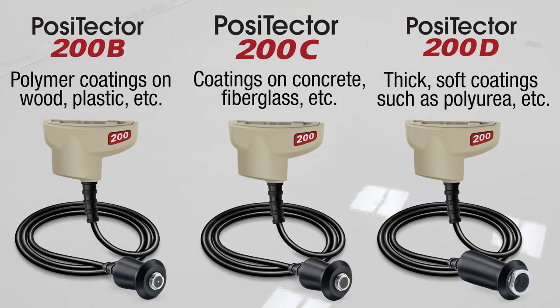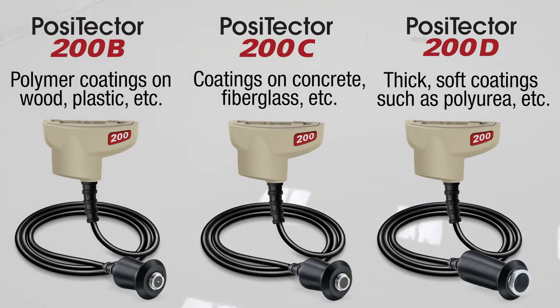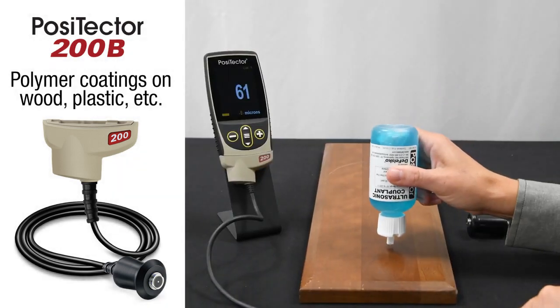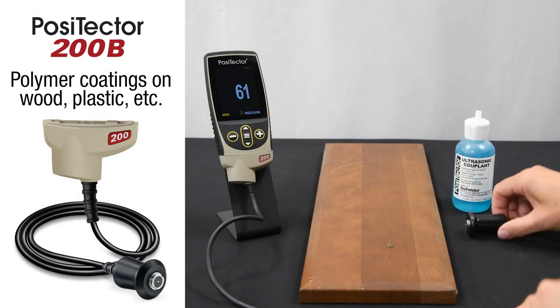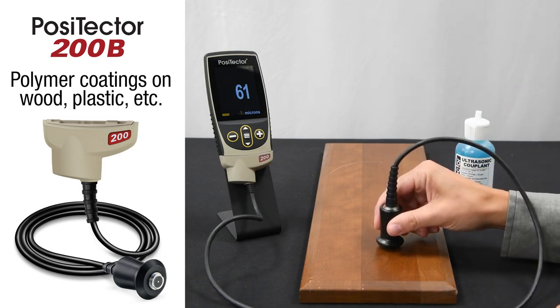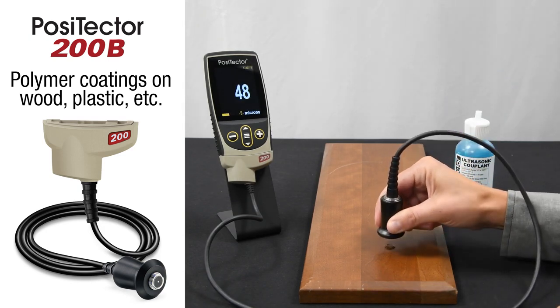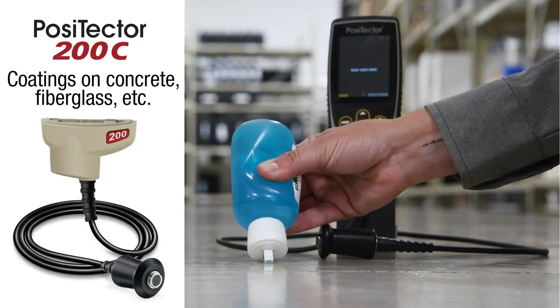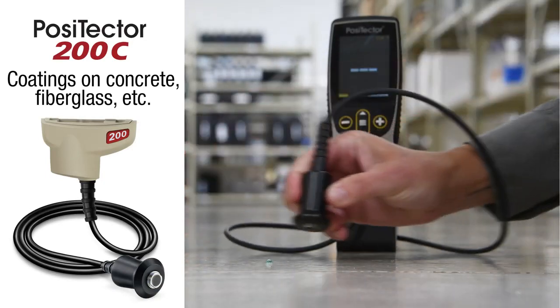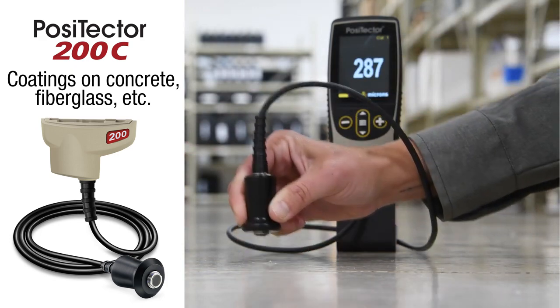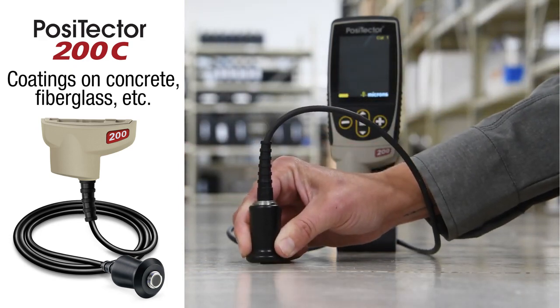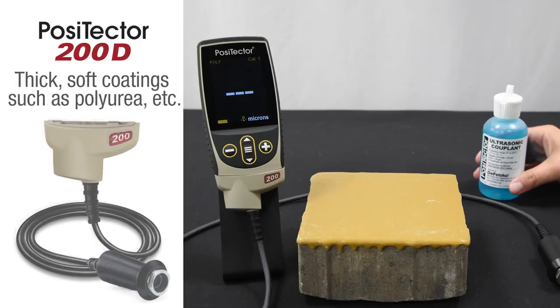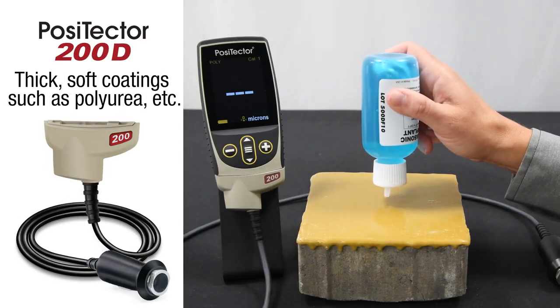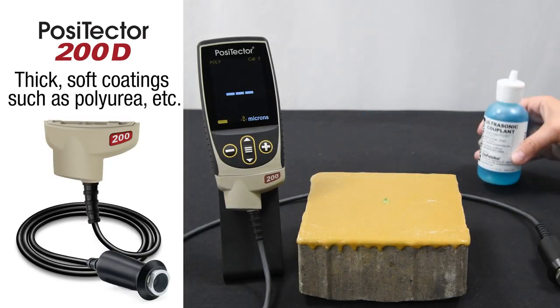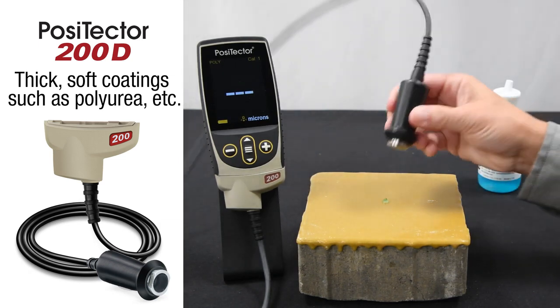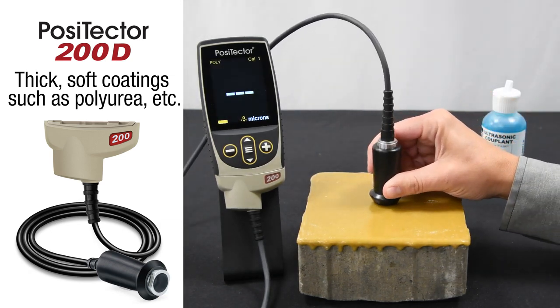3 probes are available to measure a range of different substrates and expected coating thicknesses. The Positector 200B probe is ideal for measuring thin polymer coatings on wood and plastics up to 1,000 microns or 40 mils thick. The C probe is ideal for measuring thick polymer coatings on concrete and fiberglass up to 3,800 microns or 150 mils thick. The D probe was specifically designed to measure very thick, soft coatings like polyurea, asphaltic neoprene, and thick polymers up to 7,600 microns or 300 mils.